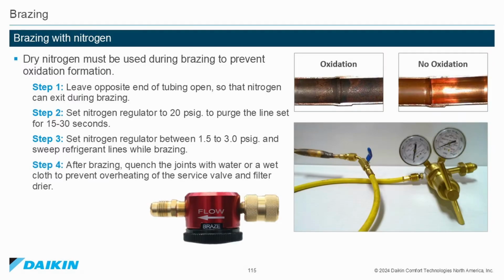Step 4. After brazing, quench the joints with water or a wet cloth to prevent overheating of the service valves and filter dryer.